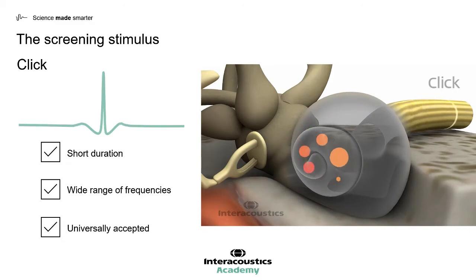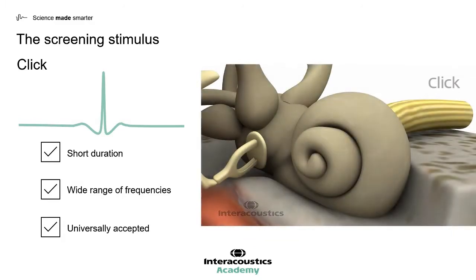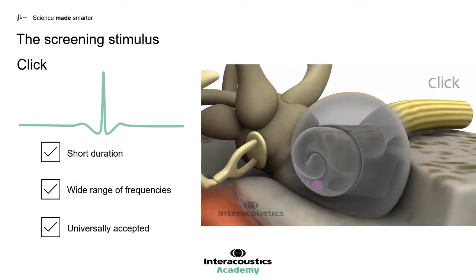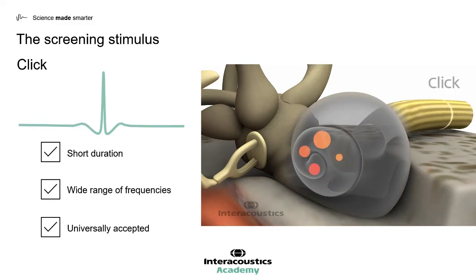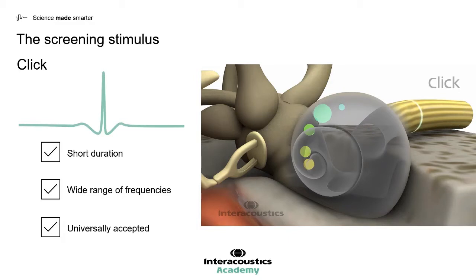The challenge associated with the click stimulus, just like in traditional ABR testing, can be displayed in the video shown on the right-hand side of the screen. Although the stimulus presents all frequencies to the cochlea at the same time, the way the cochlea is organized — from high frequency to low frequency — means that the firing of the nerve happens at different times for different frequencies. This causes a smearing of the response, and therefore lower response amplitudes on the ABR itself. The result of this is that, in addition to smaller responses, in the screening world, this will lead to longer test times.